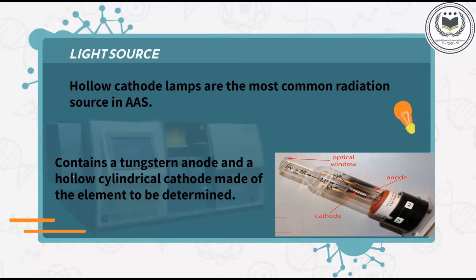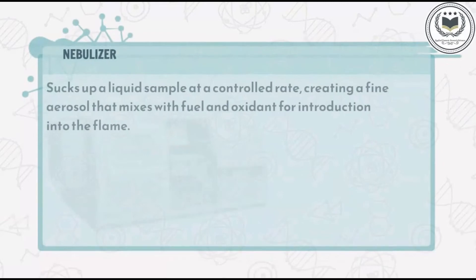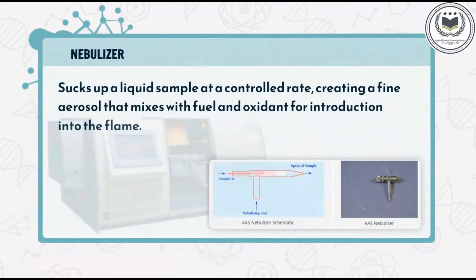The hollow cathode lamp contains a tungsten anode and a hollow cylindrical cathode made of the element to be determined. The nebulizer sucks up a liquid sample at a controlled rate and creates a fine aerosol that mixes with fuel and oxidant for introduction into the flame. Nebulization takes place as a result of the disruption of the liquid by the expanding vapor formed upon evaporation of part of the liquid in the tube.